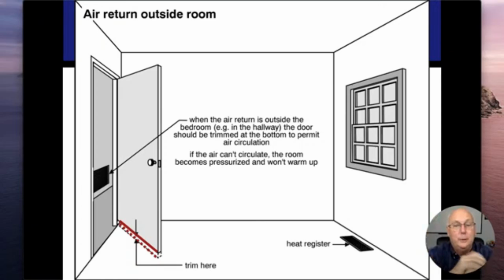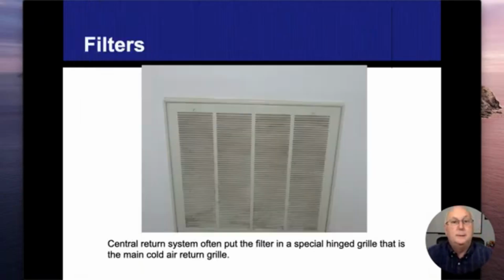One test that I do, very rarely, but I have found them where these things are problems: I make sure all the bedroom doors are closed, and I'll go into each bedroom and open the door with the furnace running or the air conditioning running, just as long as there's airflow coming through there. Then I push that door closed slowly. If I get towards the end and it pulls away and kind of slams shut, that's a no-brainer. Something's restricting the airflow out of there. It wants to flow, and we need to let it flow. So either we undercut the door more, or we have to put in another vent or something in order to let that air get through there.